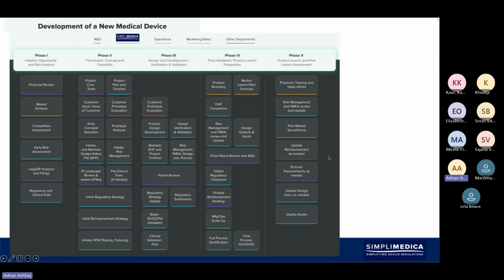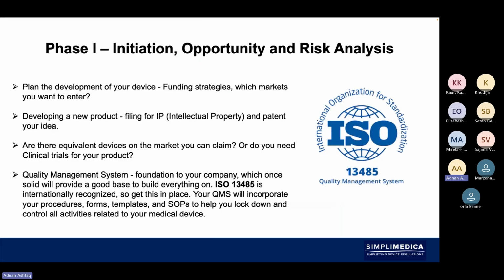And then phase five is basically keeping everything alive. So this is a cyclical process. It's not to think about medical device development as a linear process where it finishes and terminates at the point of medical device launch. It's completely live, and it must continue as long as the device is living and is active, and only upon the time where the device is terminated and maybe even ceased from existing, at that point, you have no obligations. But as long as the device is active, you still have obligations: documentation within your quality management system, adherence to ISO 13485, which is the basic medical devices quality management system requirement, and you also have to be responsible for post-market surveillance, anything like feedback and customer complaints, that needs to be looked at. And we'll also talk about this in a bit more detail now.